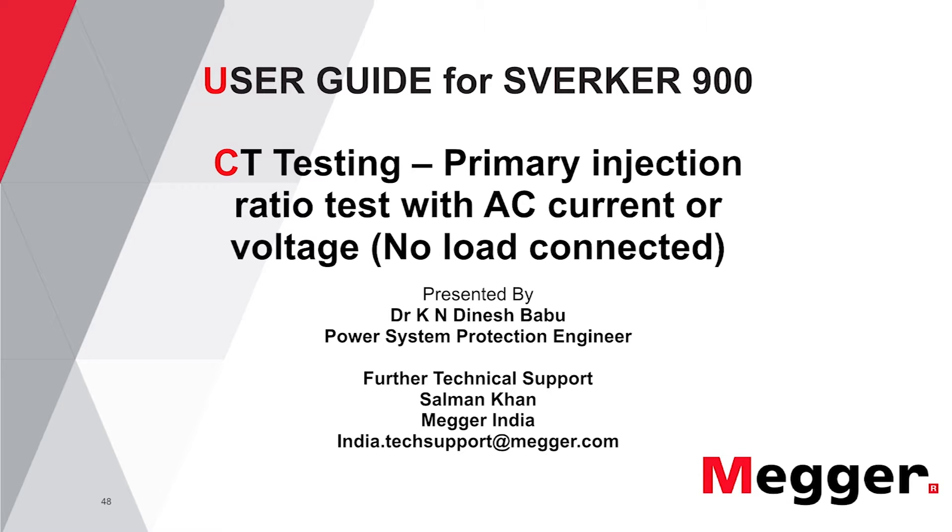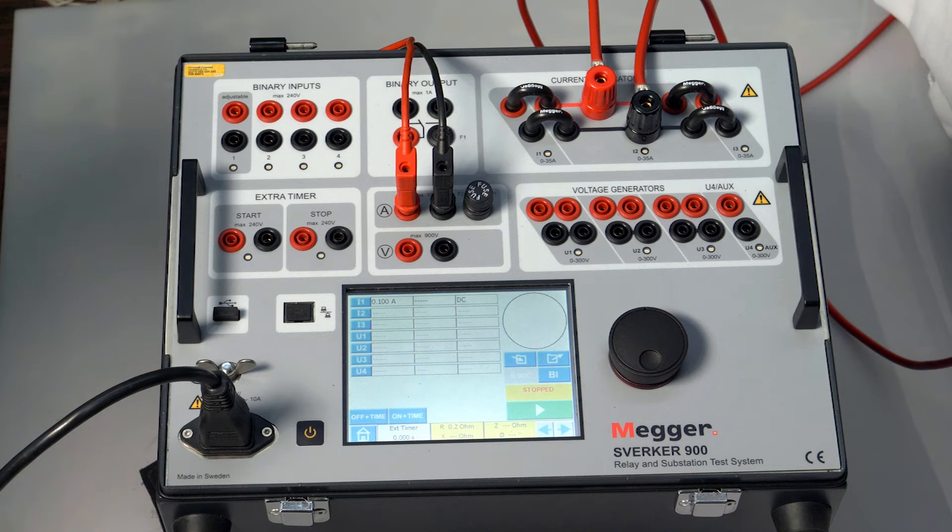CT testing, primary injection ratio test with AC current or voltage, no load connected. In the ratio test, the CT is performed by connecting the CT primary to the current source. The source has to be wired as per the recommendation to ensure it can carry the required current for the test.